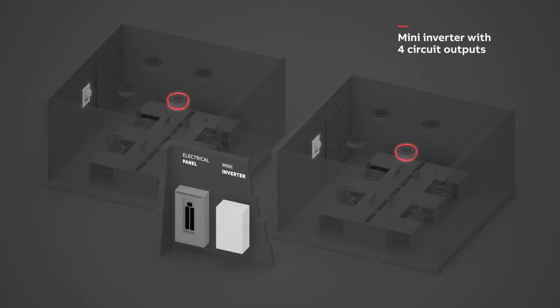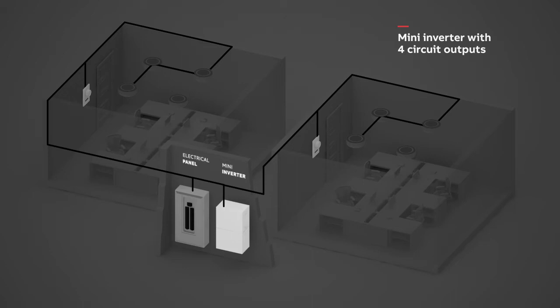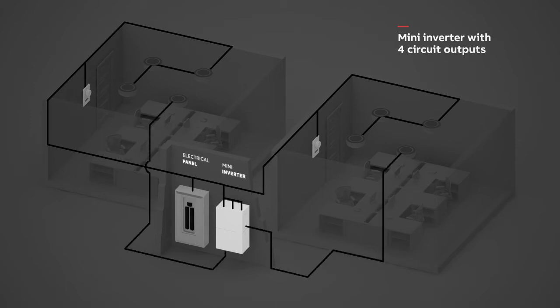Wire the unswitched input of the Mini-Inverter, all dimmers and non-emergency lights to the electrical panel. Connect Mini-Inverter input number 1 and number 2 to its unswitched input and the corresponding output to the lights that will be used as emergency lights in each zone.